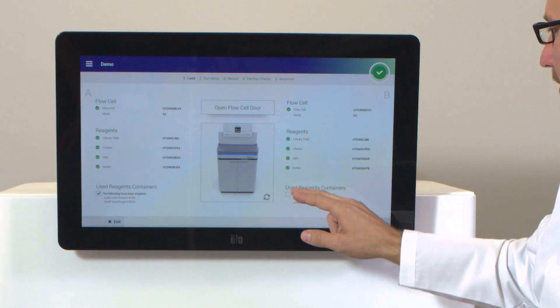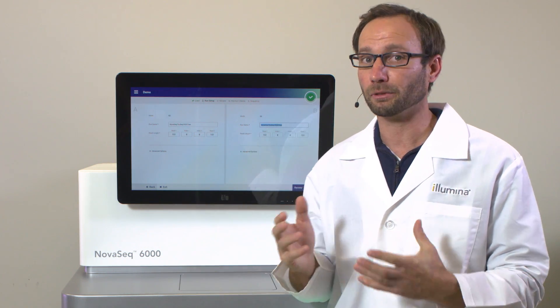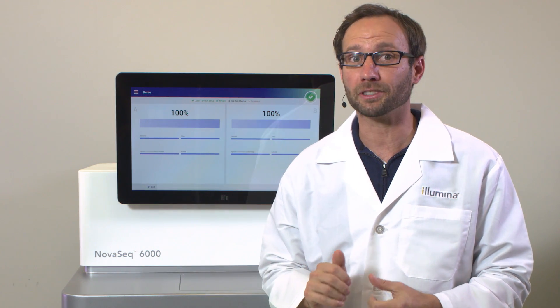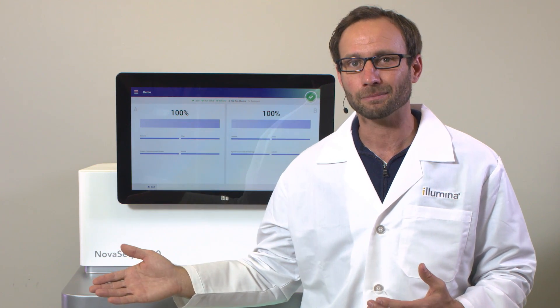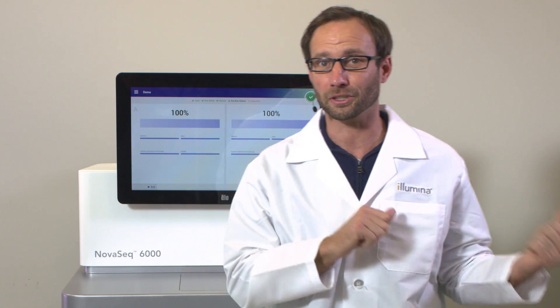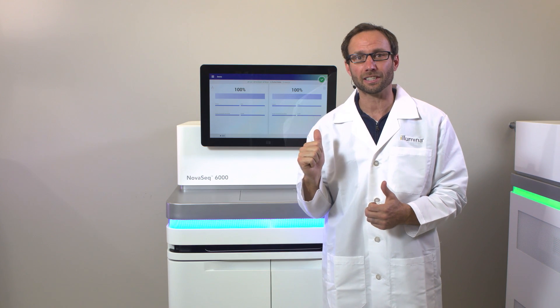I'm now going to tell the system that I've emptied out the waste trays and push the run setup button. Once you've entered all the instructions for the sequencer, you push Review. After you've reviewed your run, press the Pre-Run Checks button. The instrument will go through a series of pre-run checks designed to diagnose potential problems before the run even starts. One really cool feature is the ability to run different modes at the same time — for example, whole genome sequencing with an S3 flow cell on side A and whole exome sequencing with an S2 flow cell on side B. It's also possible to simultaneously use the instrument in online mode on one side to stream your data to BaseSpace Sequence Hub and in local mode on the other side to stream data to the local server. Once your run setup is finished and pre-run checks complete, push the Sequence button.